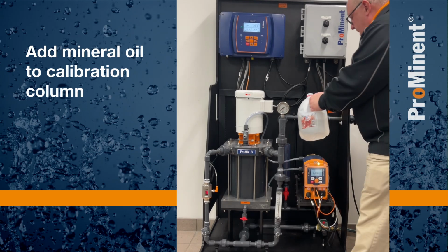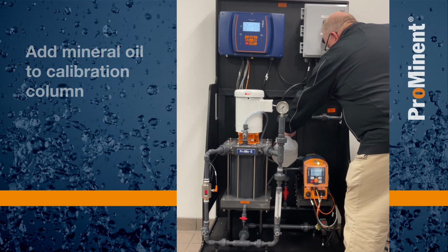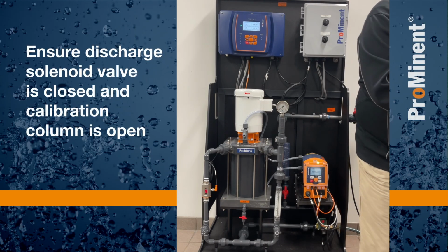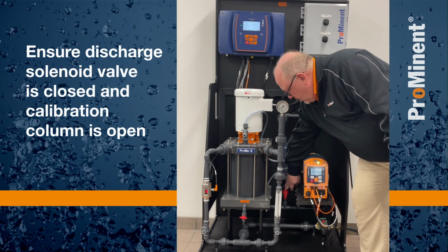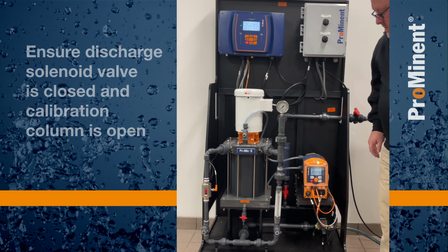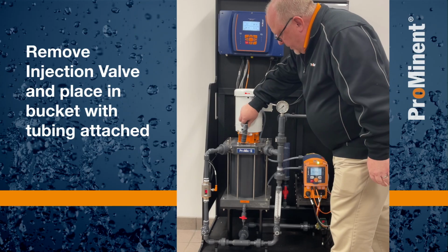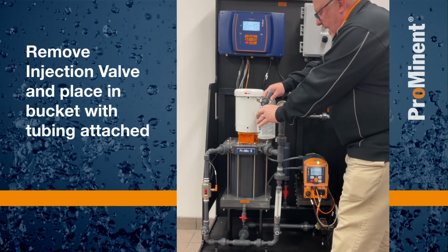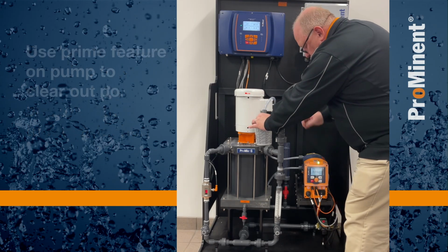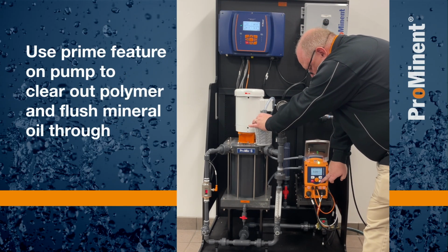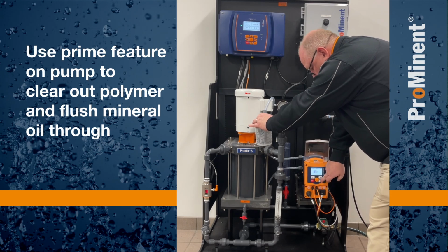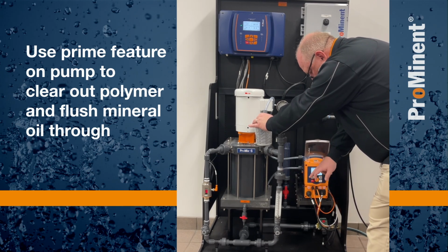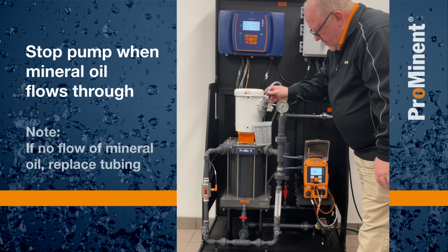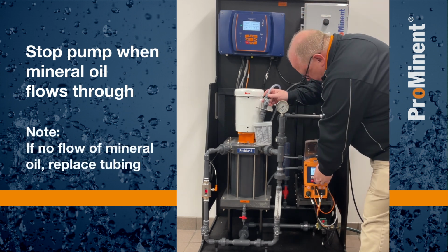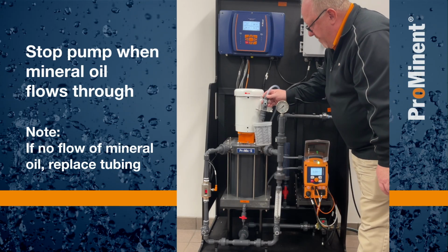So we're going to fill mineral oil into our calibration column. And we know that we're isolated to pump from there because our solenoid valve is closed. We have our calibration column open. We're going to hold that injection valve now somewhere where we can capture it. So just hold it right in on top. And we're going to use the prime feature on the pump. We're just holding that prime button, which is the lower right hand button, for a period of time. Then we're going to turn that up to allow it to pump through. So I can see that the mineral oil is starting to flow through. Once we have that, we can turn that back down, let the pump come to a stop.